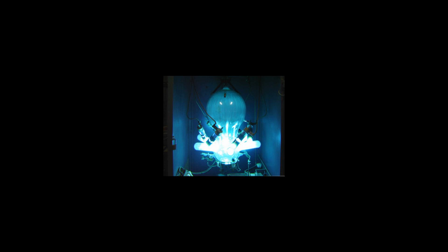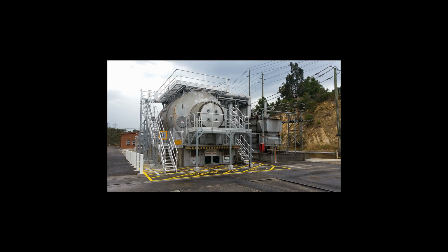Environmental hazard. Mercury compounds are toxic, highly persistent in the environment, and present a danger to humans and the environment. The use of large quantities of mercury in fragile glass envelopes presents a hazard of potential release of mercury to the environment should the glass bulb be broken. Some HVDC converter stations have required extensive cleanup to eliminate traces of mercury emitted from the station over its service life. Steel tank rectifiers frequently required vacuum pumps, which continually emitted small amounts of mercury vapor.